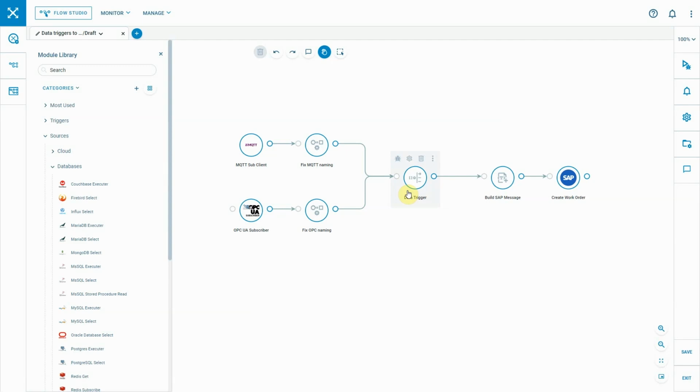We can also do basic arithmetic operations between data sources, so we can check whether the difference between two temperature sensors is above some threshold, things like that. So a lot of different conditions can be checked, and in addition to checking the actual values, we can also check that these conditions are true for a certain time, so that we don't fire triggers based on intermittent values. So we can say that we just want to fire a trigger when this condition has been met for a certain amount of time.